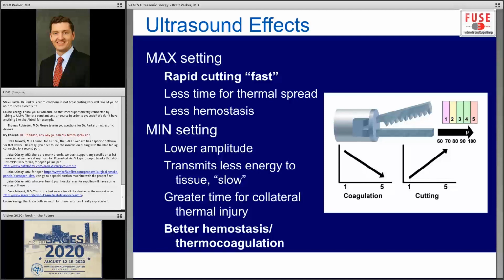Think about sawing a tree down with long strokes versus very short strokes. The max setting, again, which is a larger amount of blade excursion, results in this more rapid cutting of tissue and hence less thermal spread, which intuitively leads to minimal hemostasis. The min setting, or minimal setting, leads to less excursion of the blade, which transmits less mechanical energy to the tissue and hence less efficient cutting. However, this slow setting leads to a greater degree of collateral thermal injury and ultimately provides better hemostasis. So the min setting is excellent because it has better hemostasis.